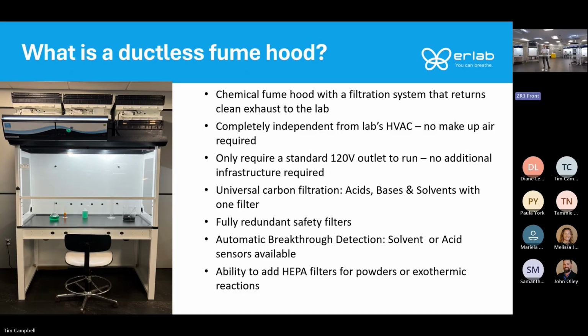But then on top of the fan, there's a backup safety redundant filter. And that's in case there's any temporary breakthrough past that main carbon filter. You're still protected by having that backup filter on the hood. And then in those white fan boxes, that's where you have breakthrough detection sensors. A solvent sensor or an acid sensor to detect breakthrough of solvents or acids, and it's going to alert you. But also by having those backup filters on the fume hood on top of the fan box, when you get an alert that there's breakthrough occurring, you're still safe because you have those backup filters capturing anything that broke through.